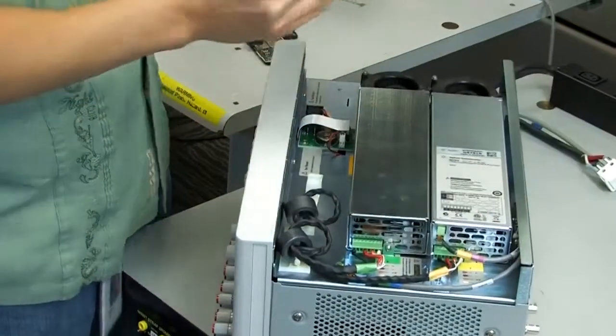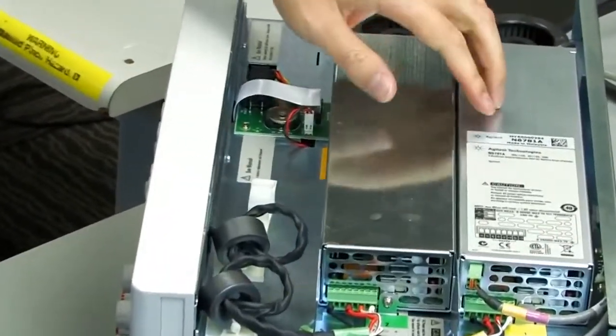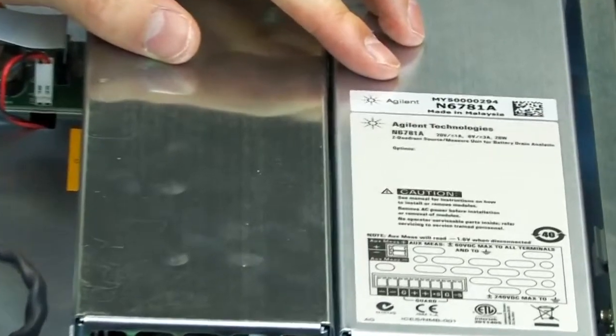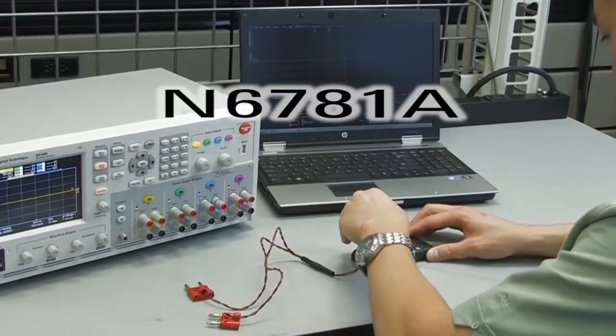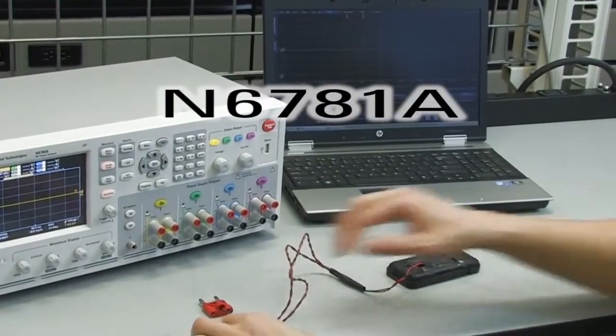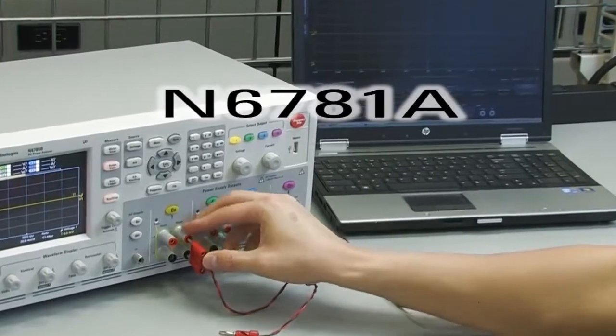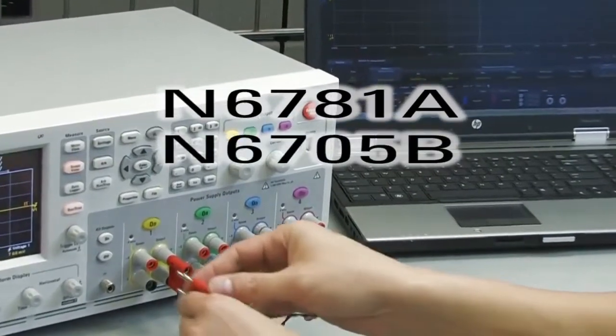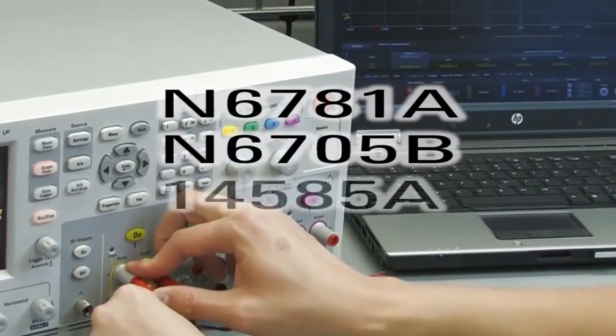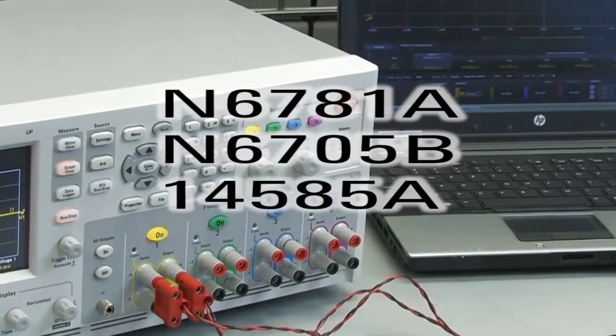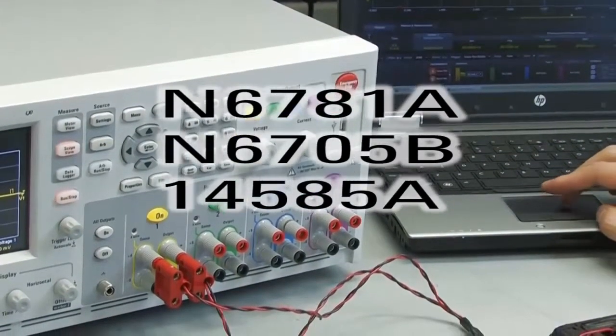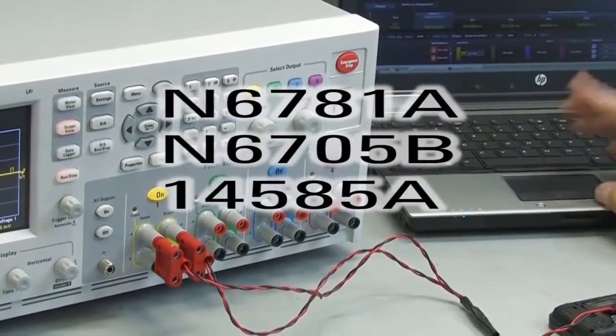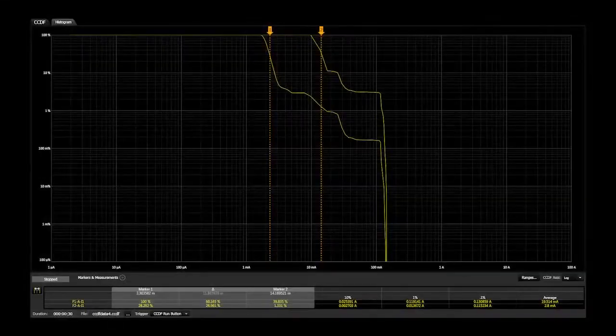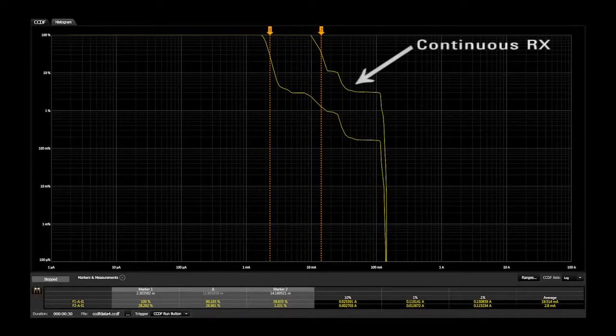Agilent Technologies has this CCDF calculation and display capability in a solution designed specifically to solve this difficult measurement task. The N6781A source measure unit is tuned for battery drain data logging and analysis. When combined with an Agilent N6705B mainframe and 14585A software, it is a superior solution for measuring and analyzing battery current drain in devices such as mobile phones. This graphic shows the CCDF display of standby current in a mobile phone during continuous receive mode.